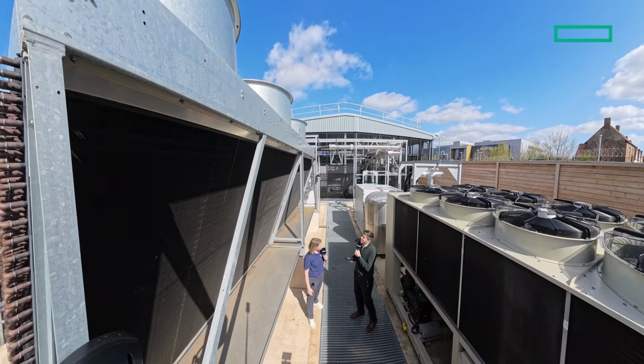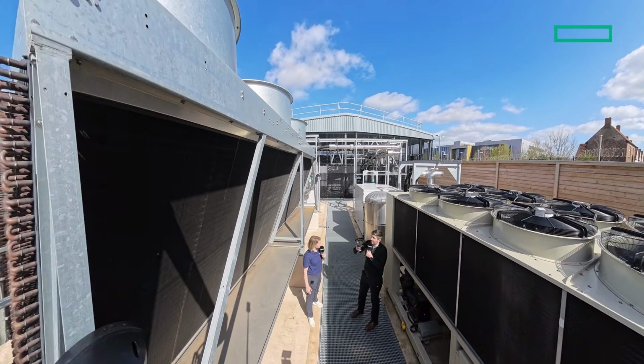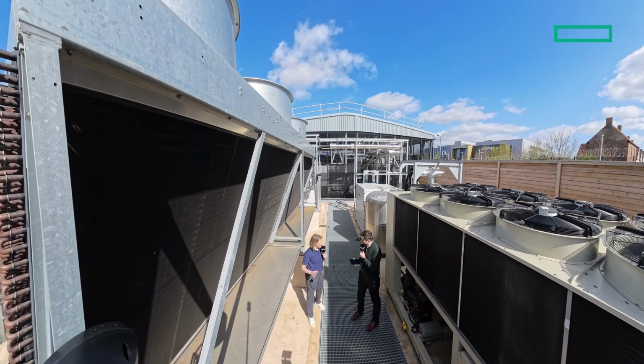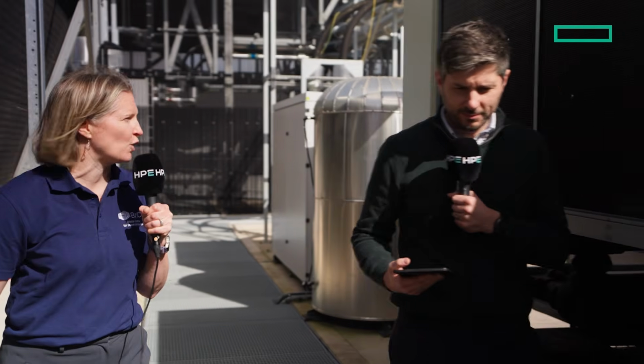And so how much energy are these fans, these radiators using? There are 2 coolers out here to cool the 2 sets of racks we've got inside. Each one uses about 16 kilowatts of electricity if running at full capacity, bearing in mind that each side of Isambard AI uses up to 2 megawatts. So 16 kilowatts to cool 2 megawatts worth of heat - that's quite efficient, not a lot of energy.